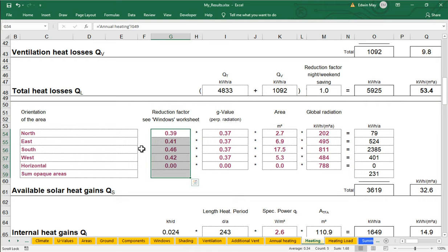So that's the way the PHPP, at least, manages all of this information. Now there are some other things that feed into the reduction factors. There are some additional reduction due to non-perpendicular radiation, as well as dirt on the surface, as well as something called a glazing fraction. So there's a couple other pieces that come into play there. But for our purposes here in this series, we want to focus on the shading reduction factors and see how those are going to strongly affect these total reduction factors for our windows.